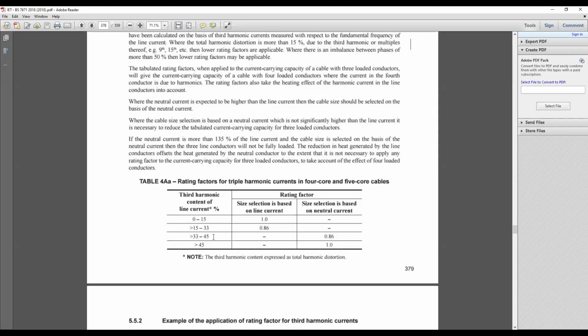So that is why we need to worry about this neutral current. So if your third harmonic content is in between 33% and 45%, you have to apply another rating factor 0.86. And if it is higher than 45%, it is 1. So in that case you do not have to apply this rating factor. So rating factor is only applicable when your current is in between 14% to 45%. So remember that.